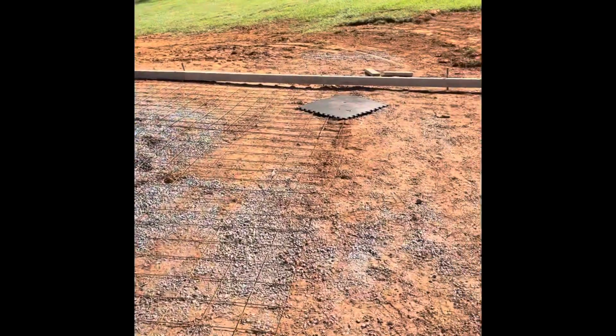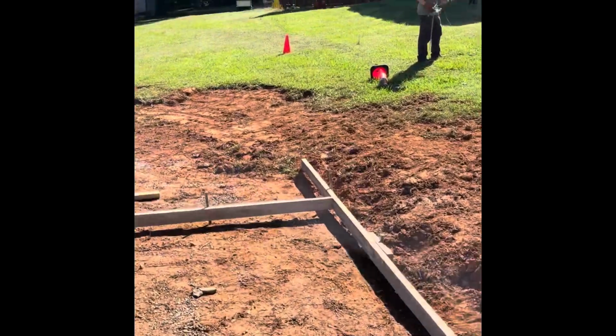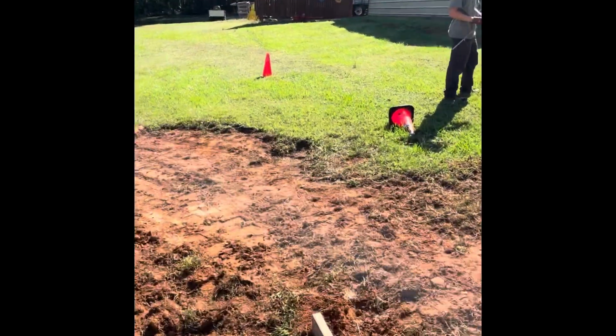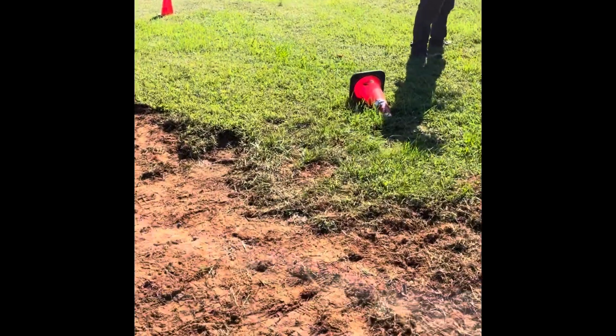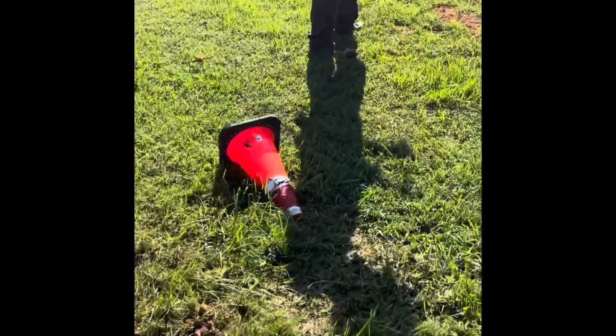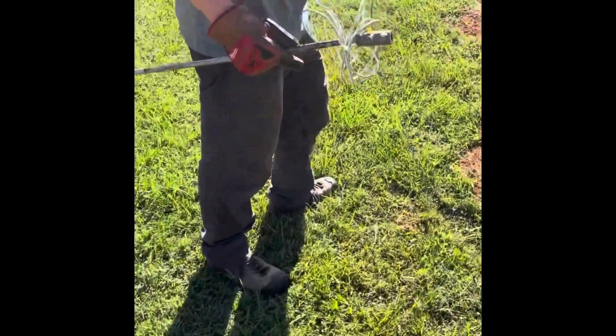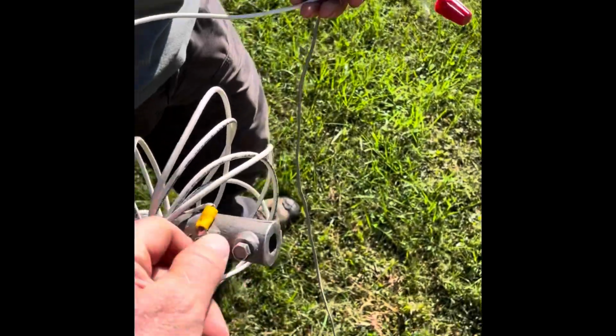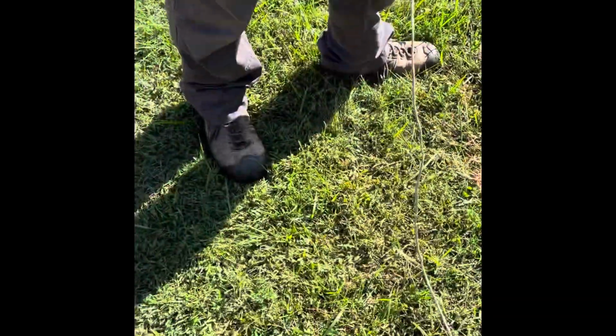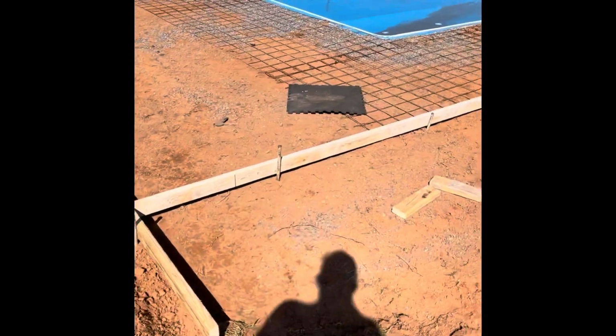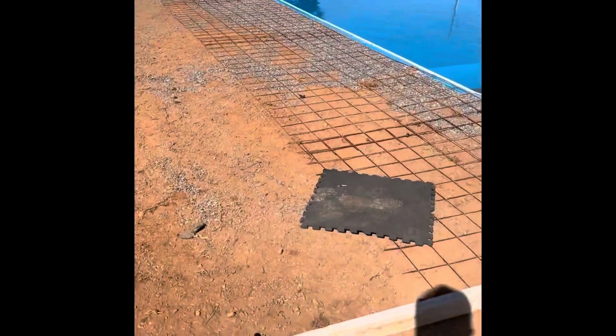What we're going to do now is we're going to stick a probe in the earth out here away from the pool. And it doesn't take much. You can use a screwdriver. We happen to use this lightning rod. There's a nice little screw on there we could connect our wire onto. Just stick it in the ground. Then we're going to go up here and we're going to check the voltage from that spot to every piece of metal or split bolts up here on the grid.